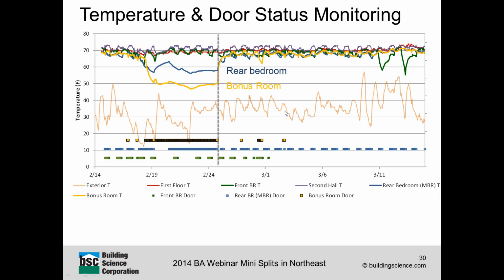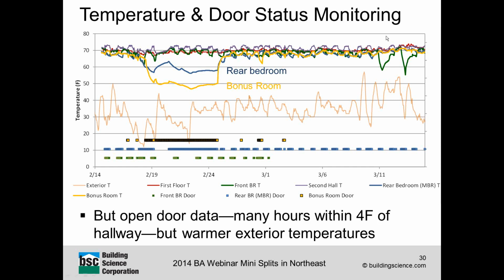But then again, you pop open these doors, and all of a sudden these temperatures pop right back up. They're definitely on the cooler side of where you would want to be, in the lower 60s, mid 60s range. But still, you can see what a huge effect door open and close state can have on the temperatures in these rooms. You can see many hours of open door data, many hours within the 4-degree temperature range, but of course these are warmer temperature conditions above freezing range.